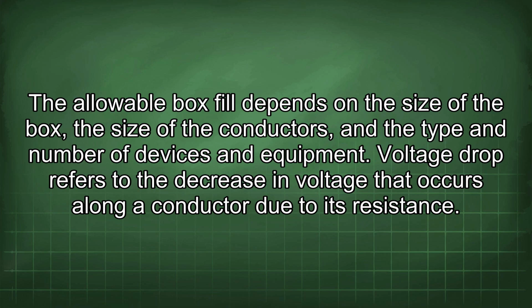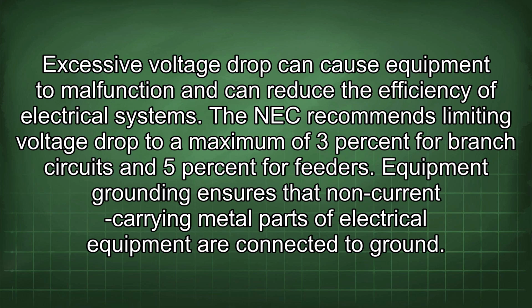Voltage drop refers to the decrease in voltage that occurs along a conductor due to its resistance. Excessive voltage drop can cause equipment to malfunction and can reduce the efficiency of electrical systems. The NEC recommends limiting voltage drop to a maximum of 3% for branch circuits and 5% for feeders.